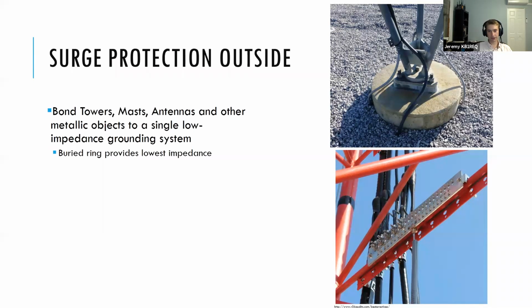So outside, the biggest thing is bonding everything using the appropriate hardware that's designed for outdoor electrical grounding. And what that does is it directs the surge right down, and most of that current is going to take that low impedance grounding system going right into the ground. That's the part we talked about before, right? Isolate and ground. This is the ground piece outside, giving it that good path to a low impedance ground system.